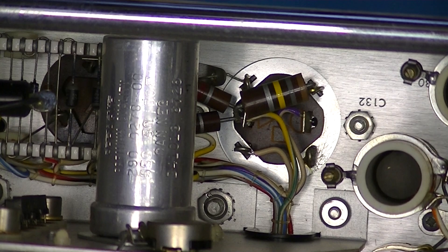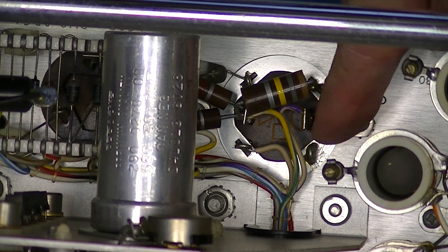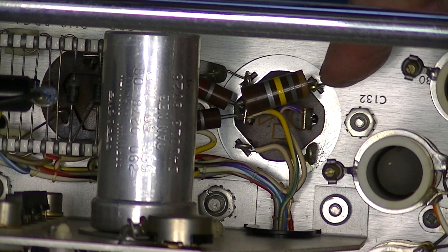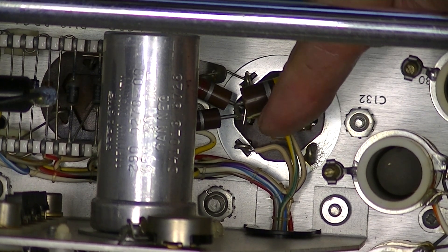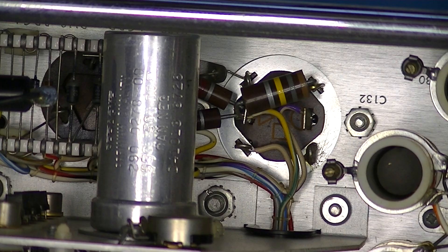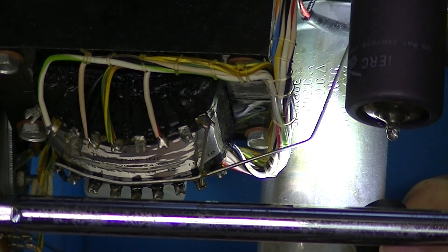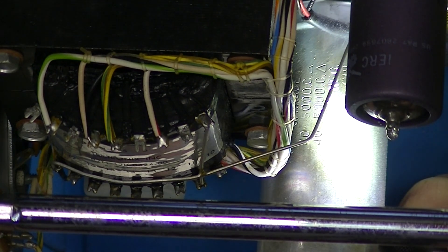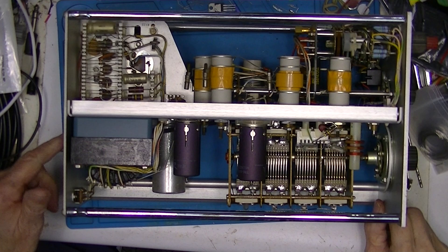Here we have one that's got four tabs connected to ground — they just push in and twist a little bit, which locks it in place — and two capacitor connections. The capacity on it is 40 and 40 microfarad at 500 volts DC. I'll find an extension cord and we'll power this up.